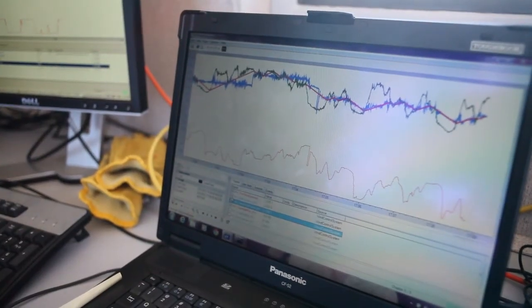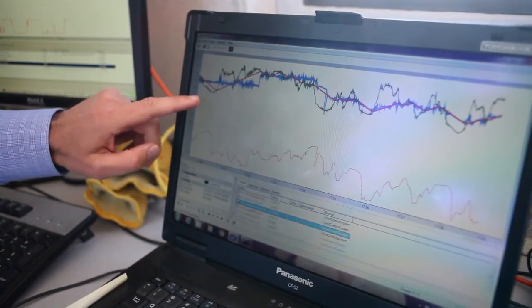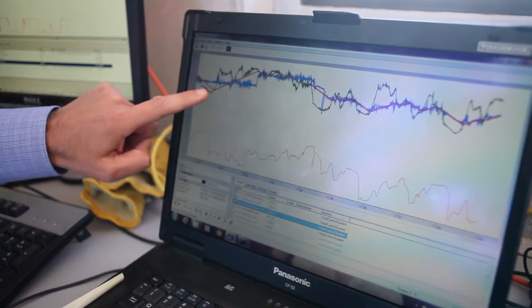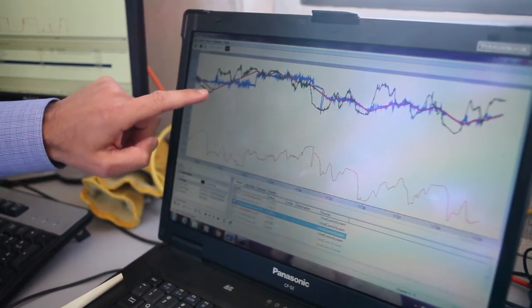The goal is 99% accuracy in that prediction. Another application is ramp control, because the grid can only absorb about 10% per minute of wind power. You want a nice controlled ramp up and a nice controlled ramp down — you don't want to go from 0 megawatts to 100 megawatts in minutes; you want to do that over a 10-minute period. With ramp control turned on, the blue line now tracks the red line, hitting the prediction both up and down even as the wind fluctuates.